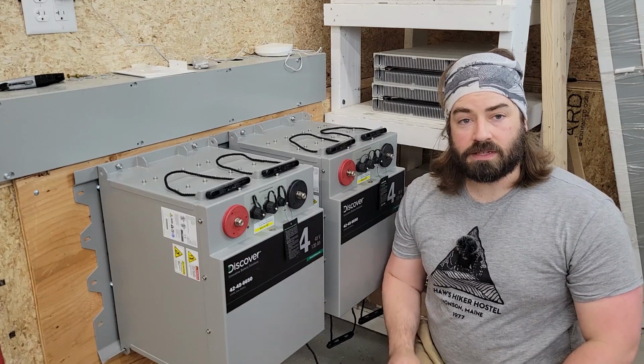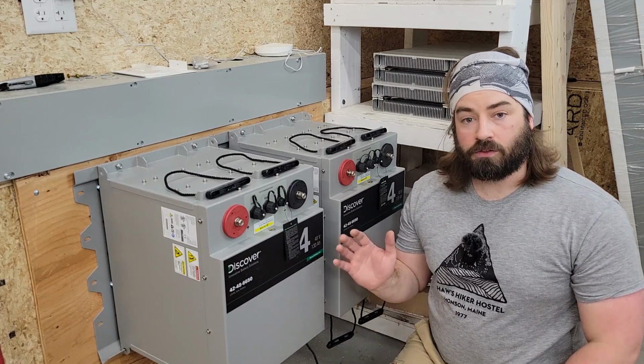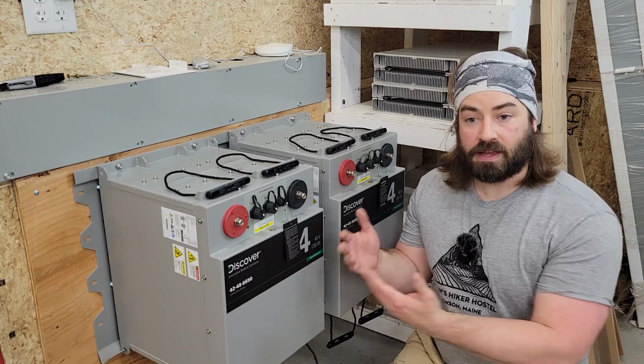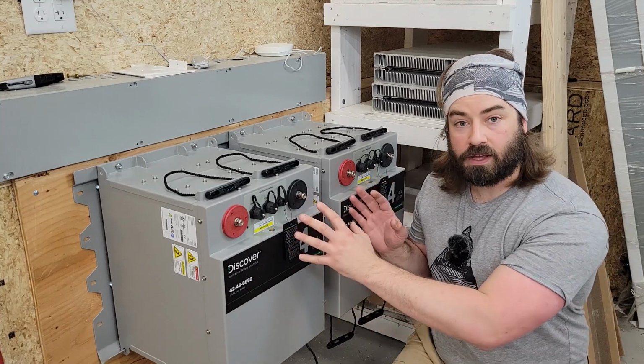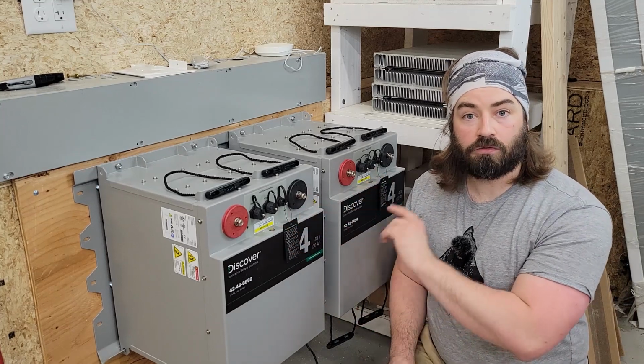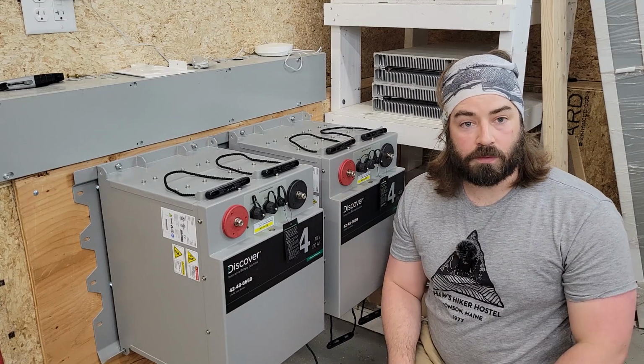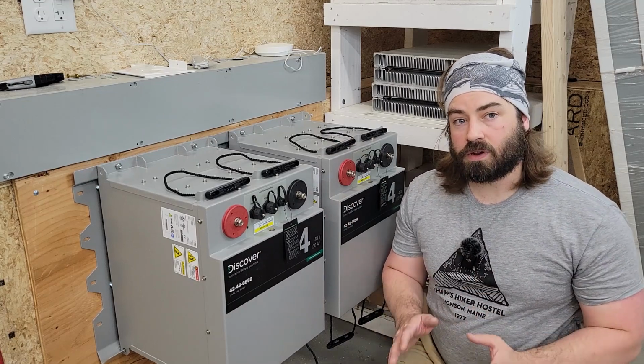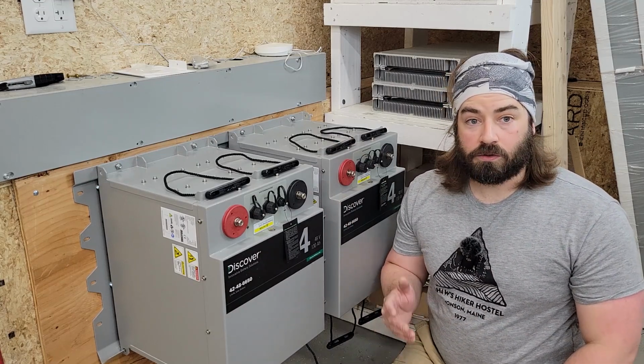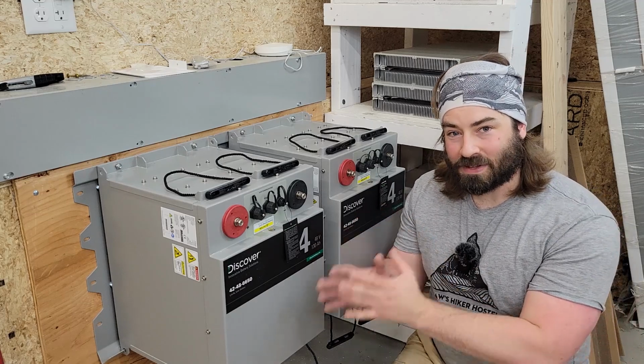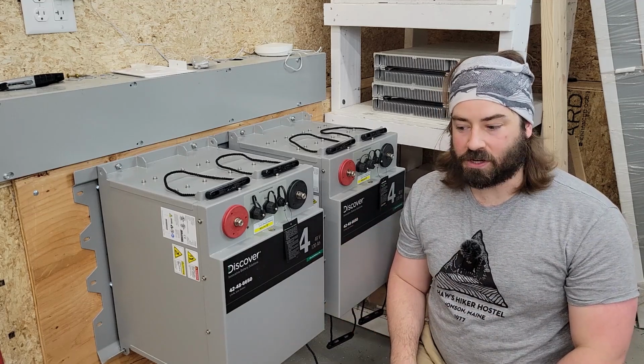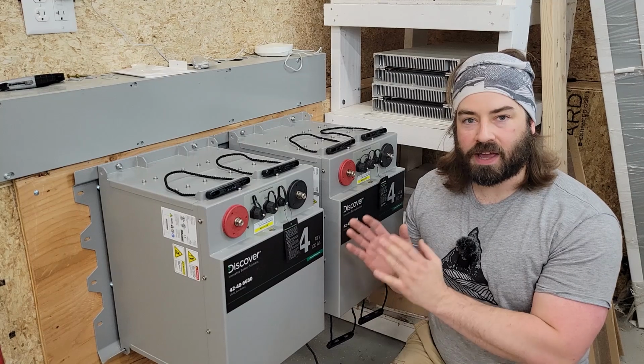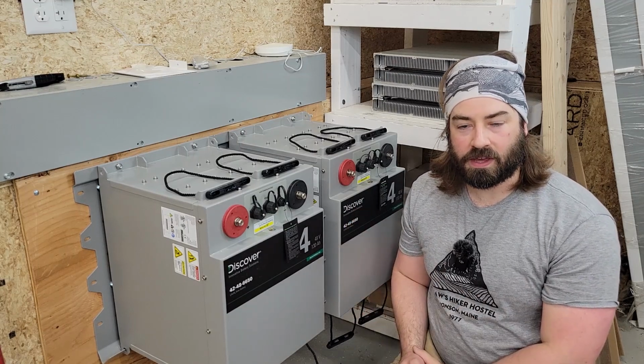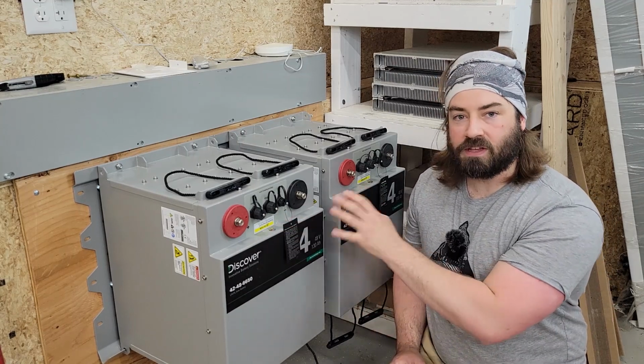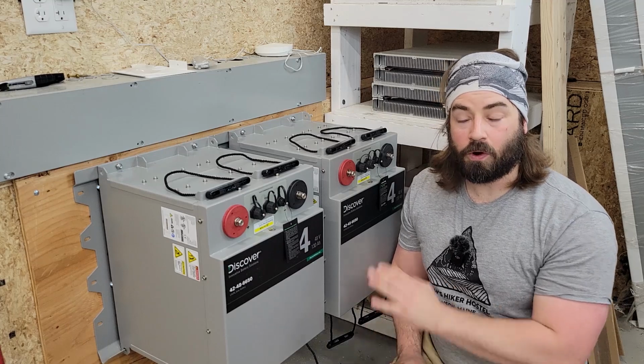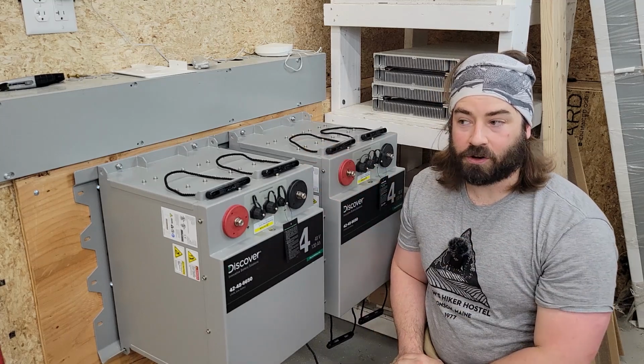The manual does say it's okay to wire 2 batteries as a daisy chain, paralleling them down here with wires and then running a single wire up to the bus bar. I'm going to demonstrate that, but I want to stress that a central bus bar is the ideal situation. Let's look at the considerations for running these together before taking them up to the inverter.